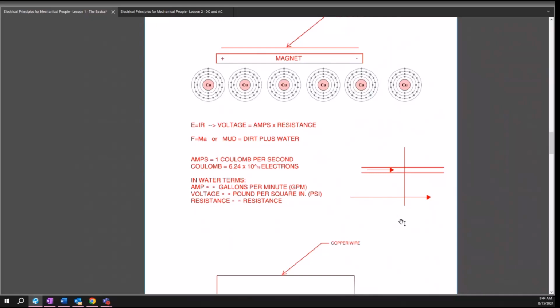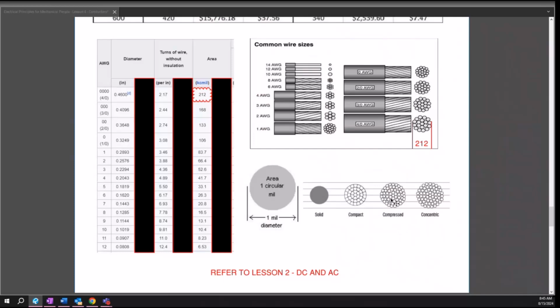They're still hitting the outside, hitting the inside. Like there's friction in there, if you want to call it that. That friction is going to cause heat, just like if you rub your hands together. If one of these electrons hit each other, or even get close to each other, they're going to start creating heat. Well, copper melts. It has a specific melting point. And if I have 200 amps going down a conductor, it's going to provide so much friction, so much heat going down there because of the I squared R loss.